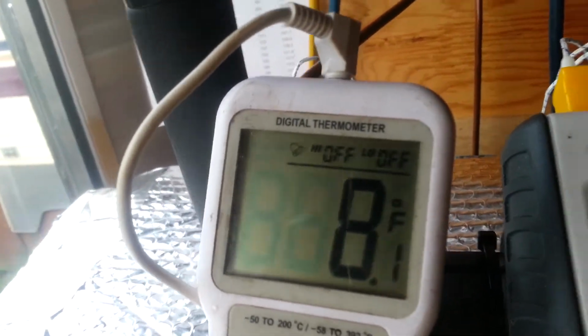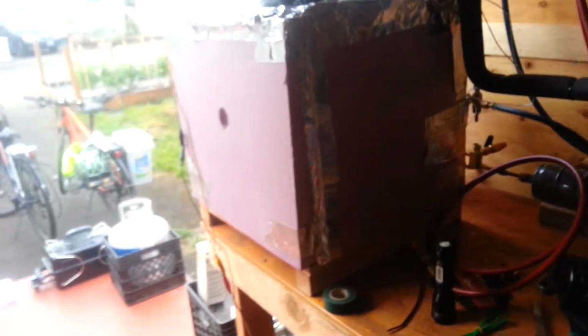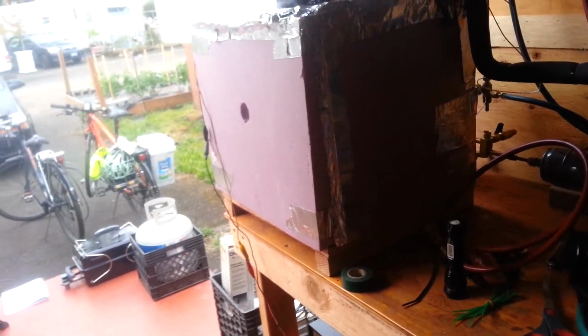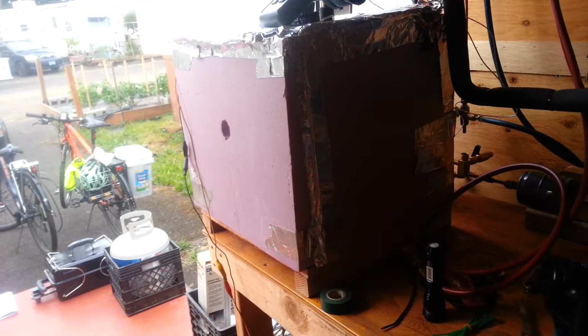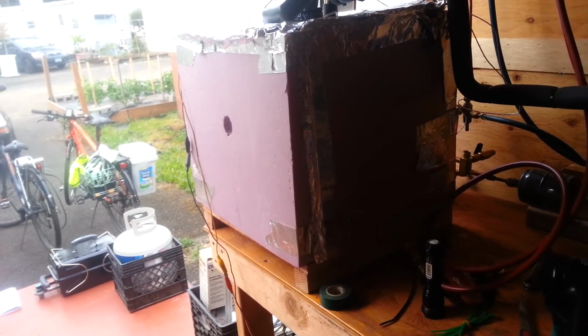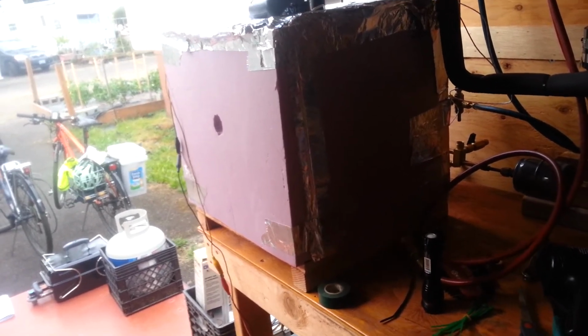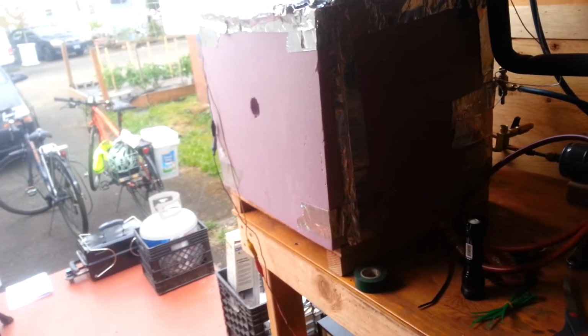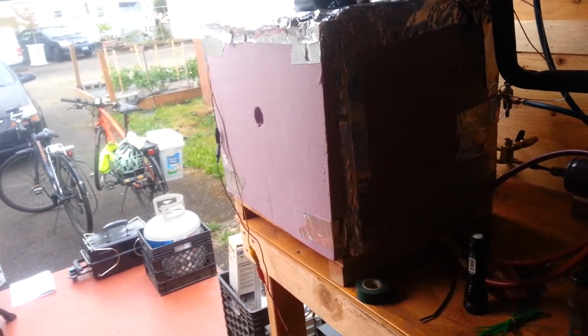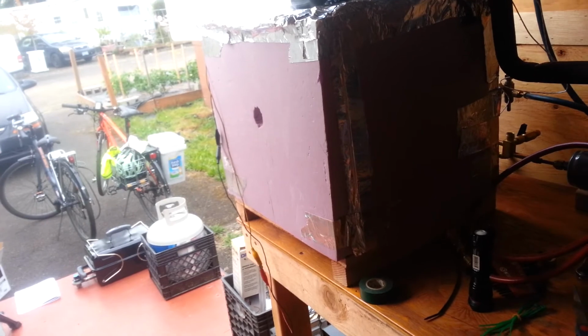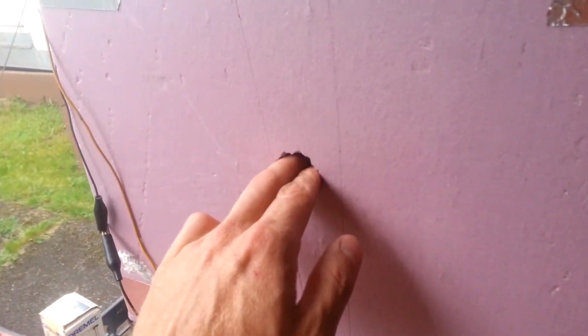There's just a probe hanging down there. I don't know how accurate it is, but it's pretty damn cold in there. The other cool thing about the flooded evaporator is that the delta T, say, rule of thumb might be 10 degrees temperature difference between the coil and the medium that you're cooling. Say it's a cooler or refrigerator or something, in order to get enough heat transfer across it.